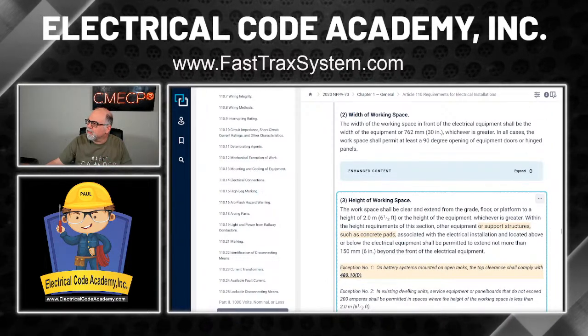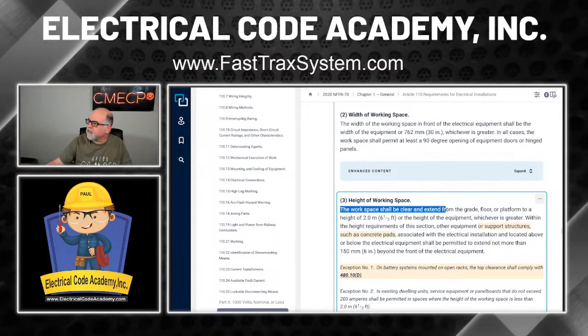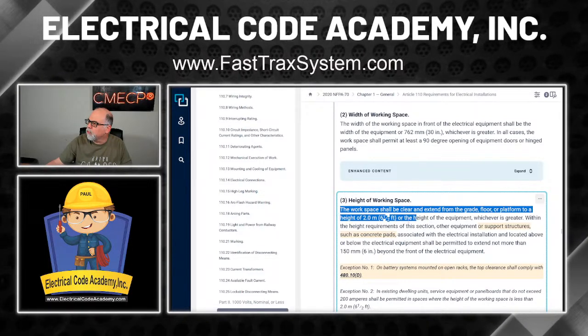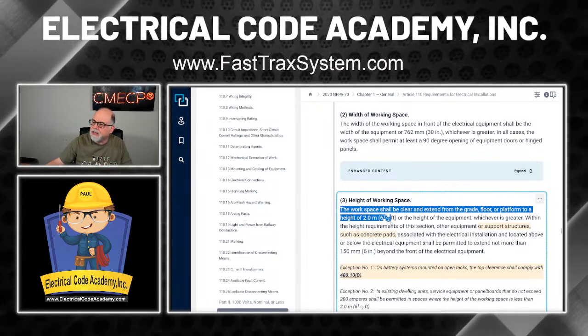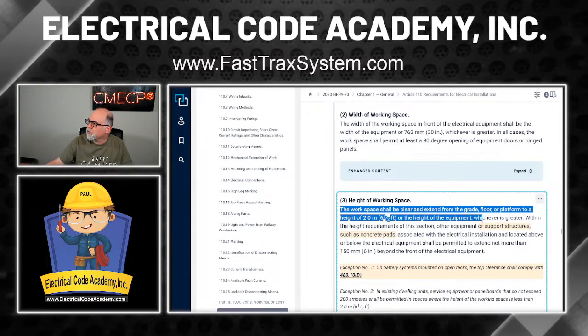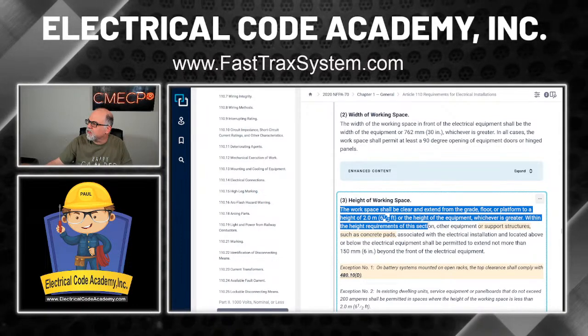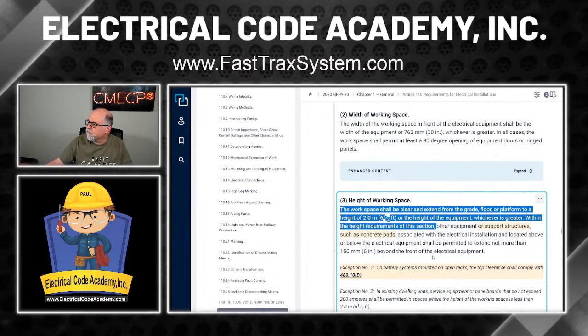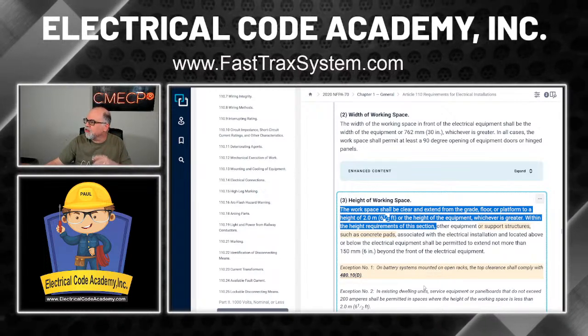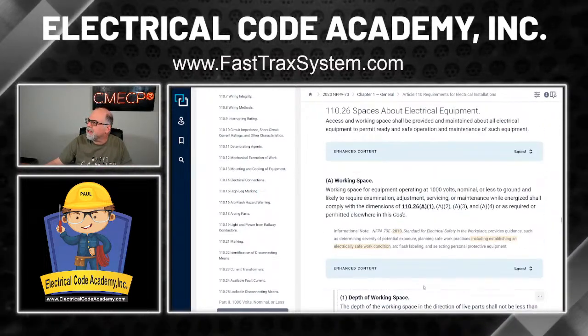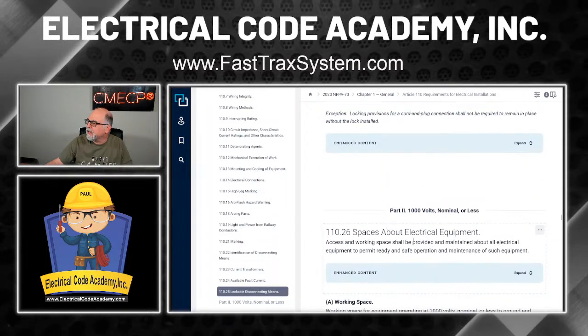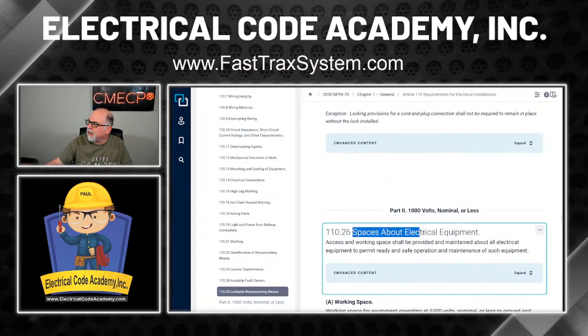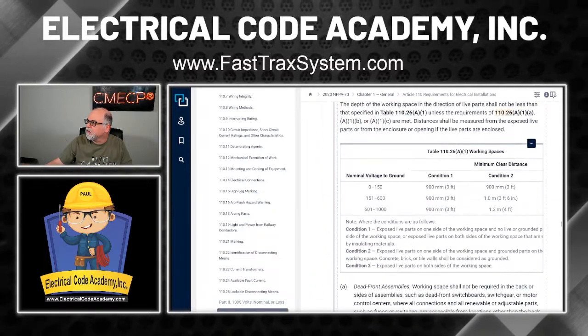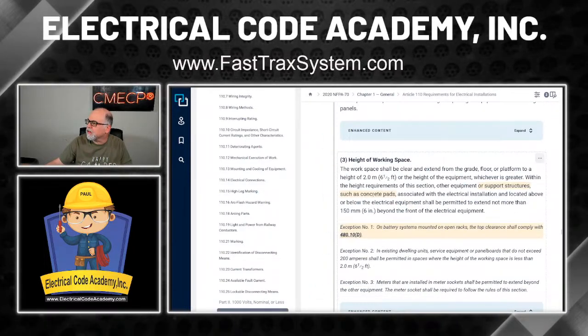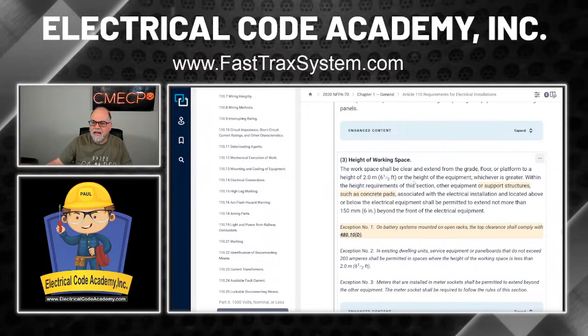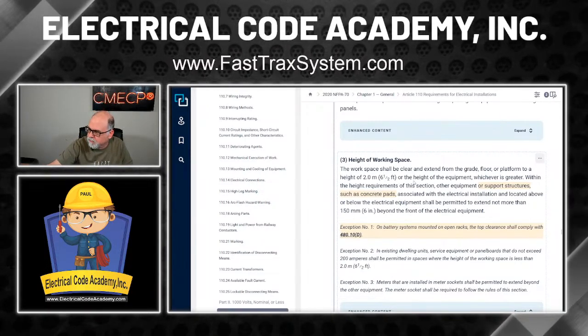Okay, it says the working space shall be clear from the grade, floor, or platform to a height of 6.5 feet, or the height of the equipment, whichever is greater, within the height requirements of this section. Okay, so if you go back and look at it, and also just so we're clear, let's go back to the beginning here. You notice that it is about all electrical equipment. Okay, so just wanted to make sure we're clear on that. All right, so it looks like 6.5 feet. Okay, so let's come back to our question.